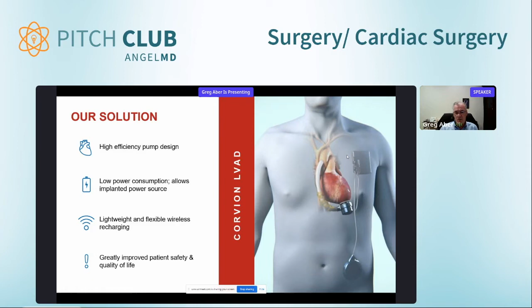And because it's not holding much energy, we're able to wirelessly recharge it, similar to an iPhone, in a very convenient way for the patient, with a lightweight device requiring no power cords, no contact with the skin. So why is our pump so efficient, right? I mean, there's a lot of LVADs that have been developed over the past few decades. We focused on a different design than basically anyone has ever attempted, in which the pump is separate from the motor that drives it. And so we're able to have a very novel pump impeller geometry that drastically reduces the torque required to spin the impeller and therefore the power.